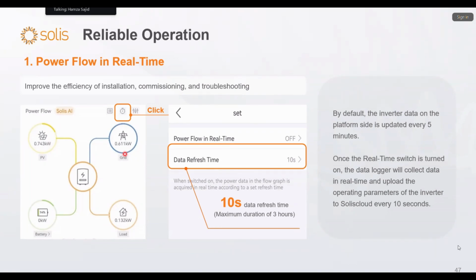Once the real-time switch is turned on, the data logger will collect the data in real time and upload the operation parameters of the inverters to Solis Cloud every 10 seconds. By default, it is 5 minutes, but if you turn on the real time, it can go up to 10 seconds for a maximum of 3 hours.